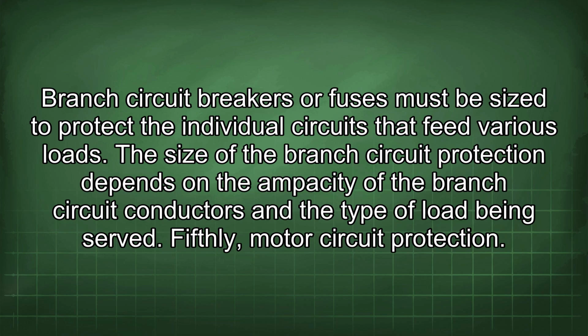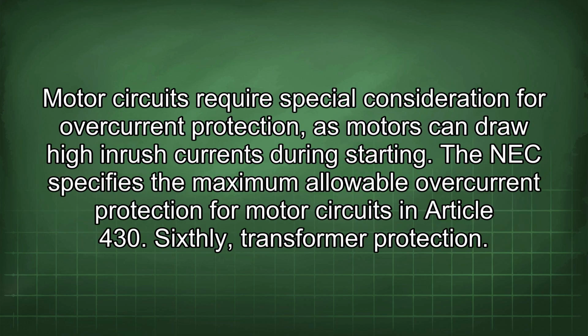The size of the branch circuit protection depends on the ampacity of the branch circuit conductors and the type of load being served. Fifthly, motor circuit protection. Motor circuits require special consideration for overcurrent protection, as motors can draw high inrush currents during starting. The NEC specifies the maximum allowable overcurrent protection for motor circuits in Article 430.